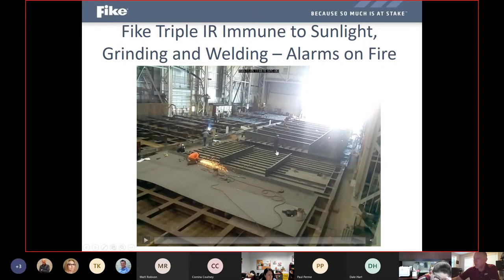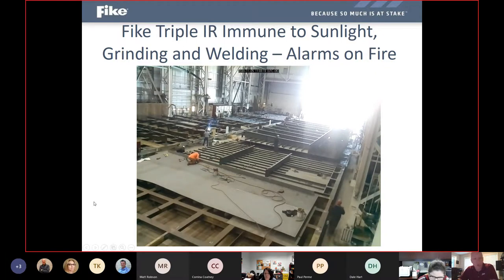But in the middle of the screen, we've got a gentleman who's going to light a traditional blowtorch and put an actual flame to a small piece of product at a pretty good distance away. And you'll see when I play the video here that the detectors are ignoring all of those other sources, which aren't fires. But as soon as that gentleman starts to strike his little torch and light a little piece of product on fire, you'll see the screen start to blink where it recognized that as an actual potential fire and triggered an alarm. And then the onboard HD camera immediately captured that alarm to video to show what it was and to justify the activation.